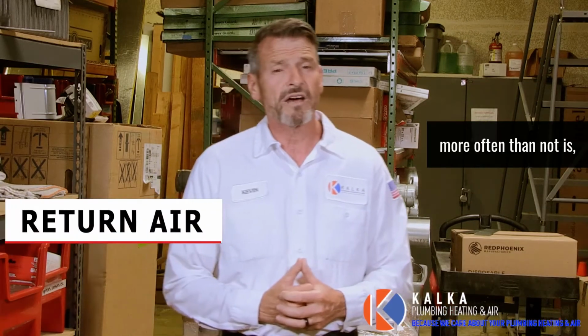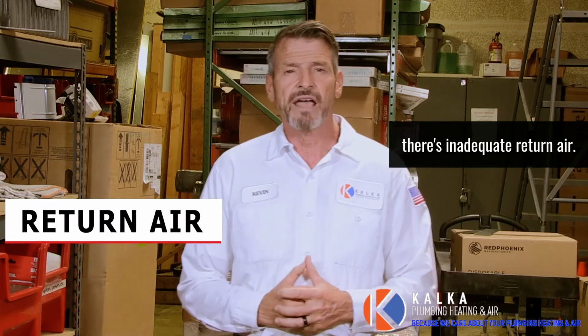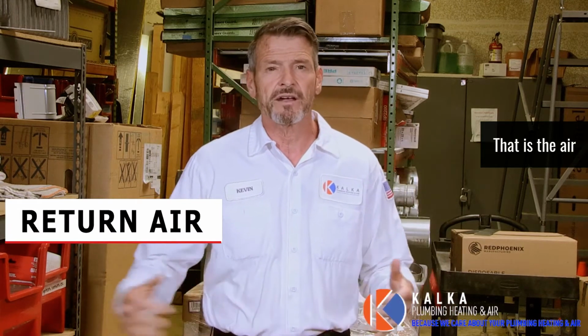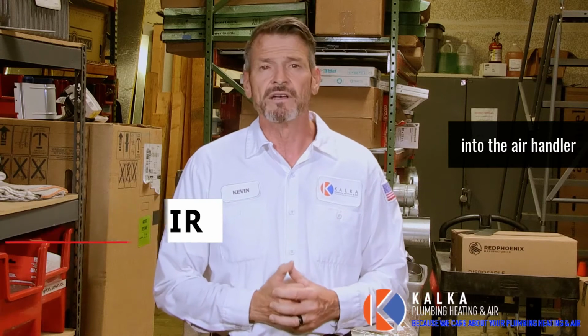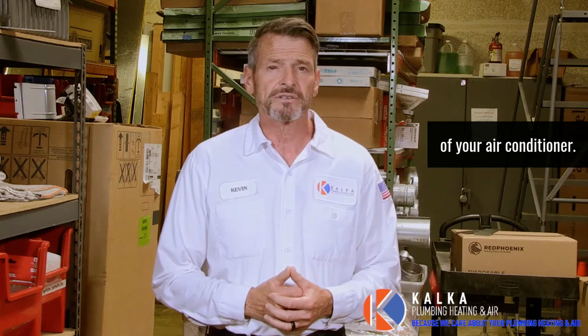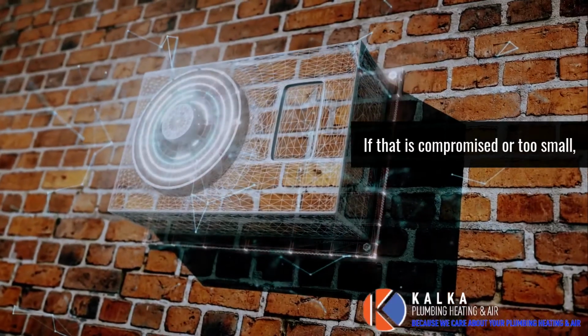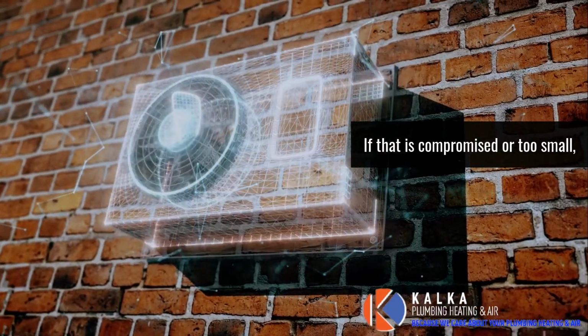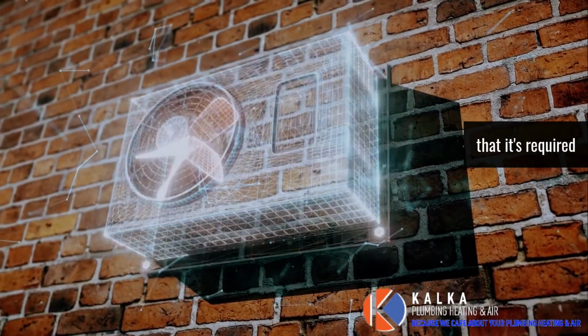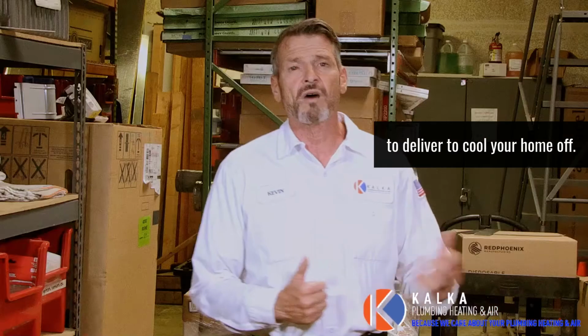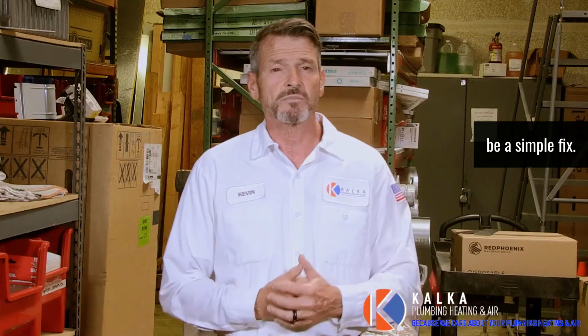Another item, more often than not, is inadequate return air. That's the air that's returned back into the air handler of your air conditioner. If that is compromised or too small, it will not deliver the airflow that's required to cool your home off, and that can oftentimes be a simple fix.